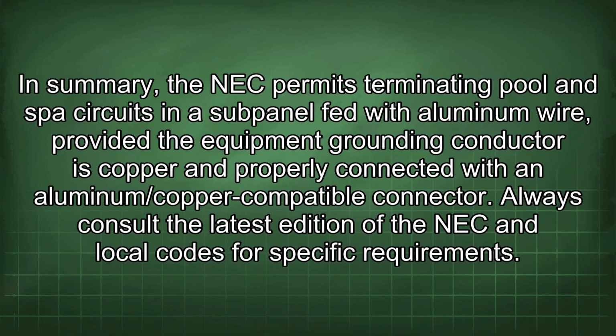In summary, the NEC permits terminating pool and spa circuits in a subpanel fed with aluminum wire, provided the equipment grounding conductor is copper and properly connected with an aluminum/copper compatible connector. Always consult the latest edition of the NEC and local codes for specific requirements.